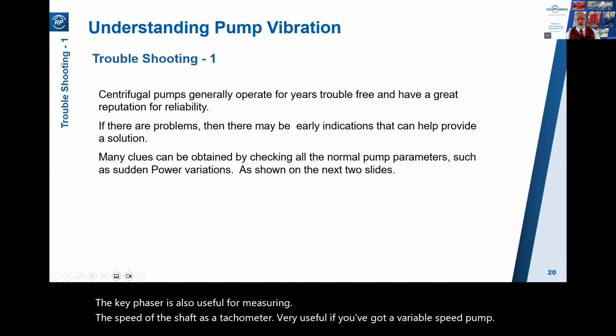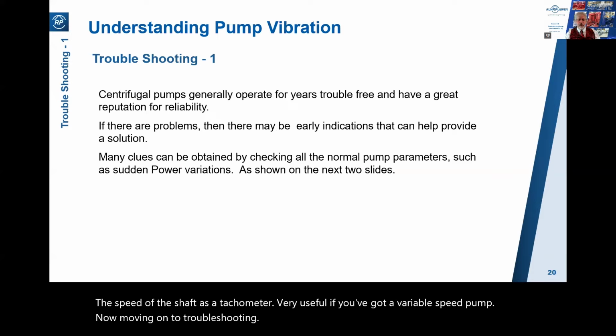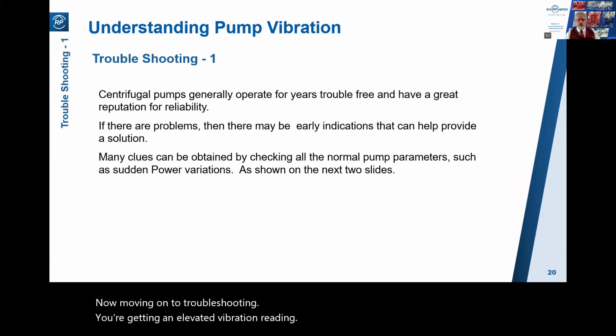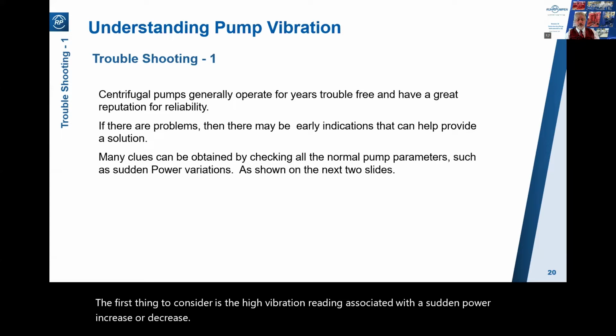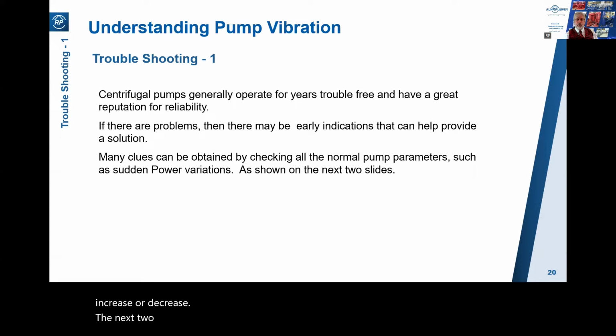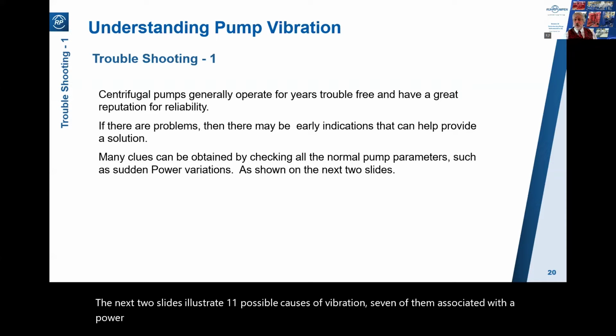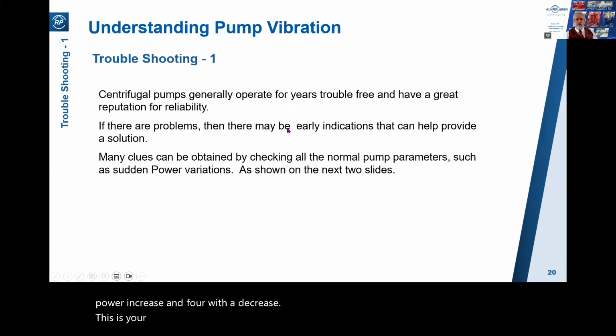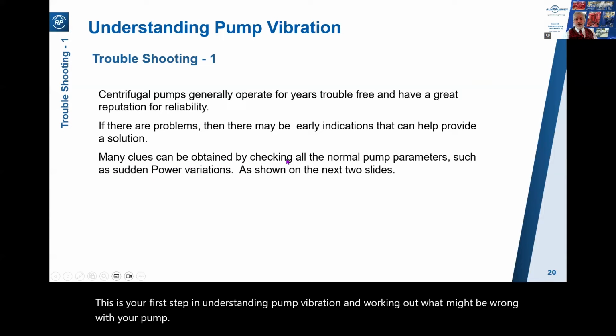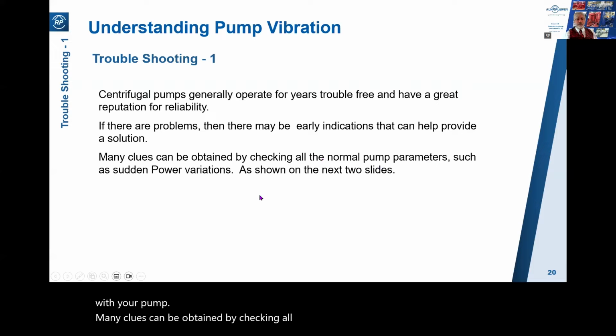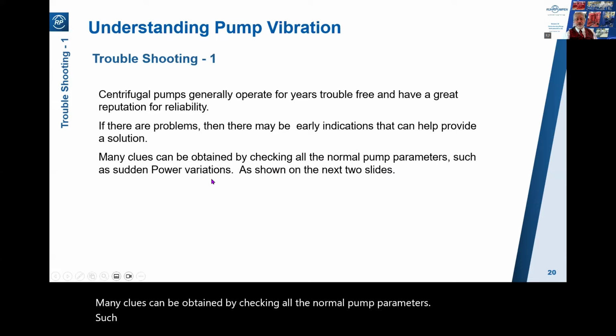Now moving on to troubleshooting. You're getting an elevated vibration reading. Well, the first thing to consider is whether the high vibration reading is associated with a sudden power increase or decrease. The next two slides illustrate 11 possible causes of vibration, 7 of them associated with a power increase and 4 with a decrease. This is your first step in understanding pump vibration and working out what might be wrong with your pump. Many clues can be obtained by checking all the normal pump parameters, such as sudden power variations.